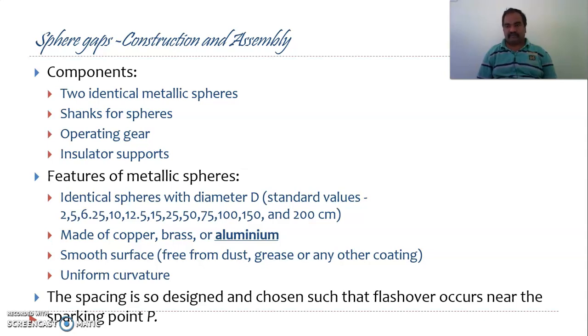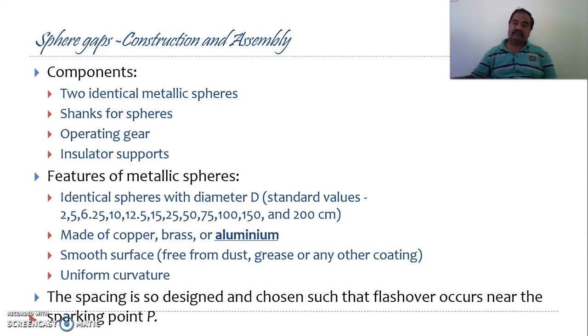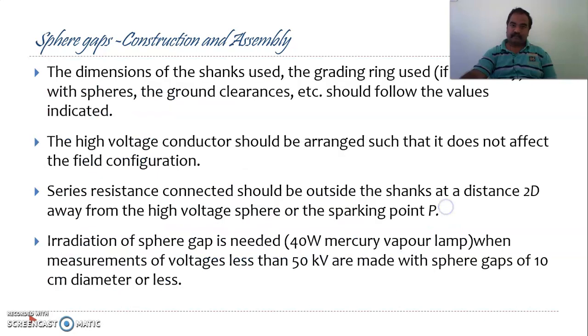There are certain features of the metallic spheres to concentrate on. The two spheres must be identical and their diameters must be the same — standard diameter values are specified. They are usually made of brass, copper, or aluminum; aluminum is generally used as it is cheapest. Make sure the surface of the spheres is free from dust, grease, or any other material. They must have a very smooth surface with uniform curvature, and the spacing is designed such that flash-over occurs near the sparking point only.